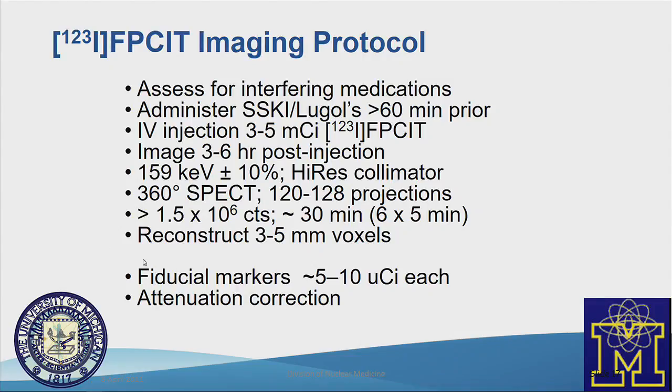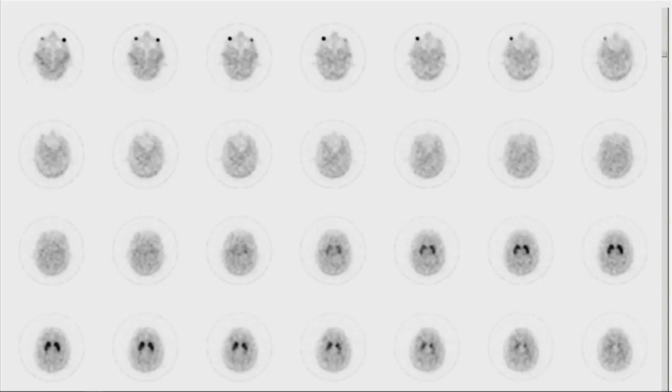And then the other issue that's not dealt with often is attenuation correction. And of course, you have to attenuation correct these images. The question is how. If you do an assumed attenuation using Chang, you will get different quantitative values than if you do a measured attenuation with a CT scan. Not sure whether that's really critical or not unless you're going to employ quantification.